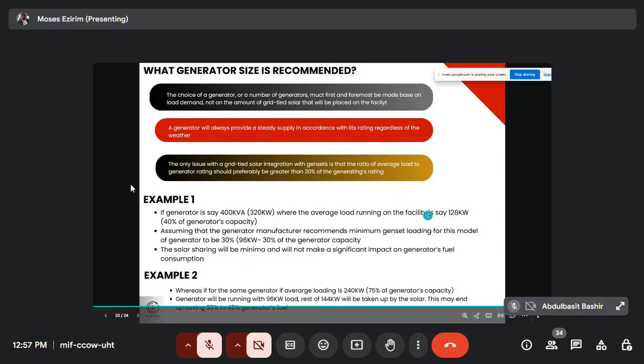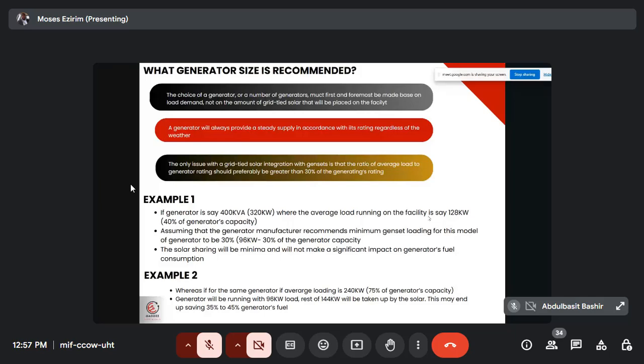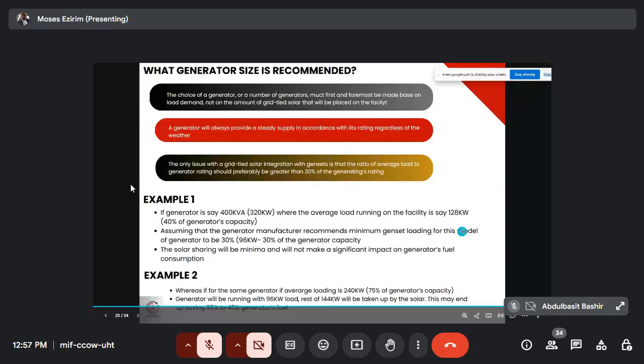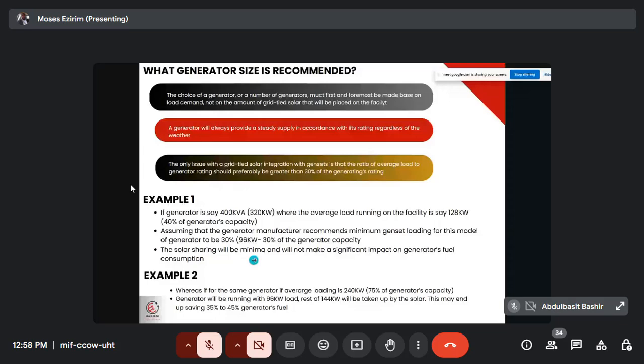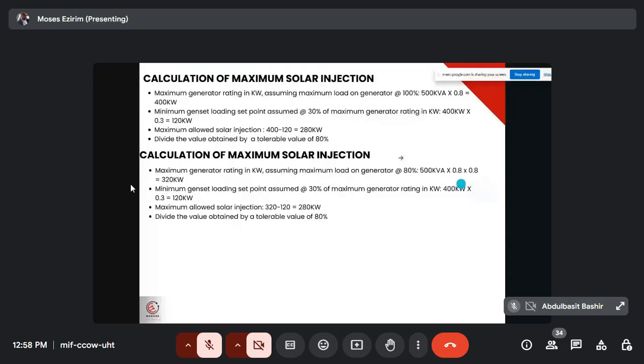Now look at the last example. Whereas if, for the same generator, the average load is 240, the generator will be running 96, that's the 30%. The rest, which is 144 kilowatt, will be taken up by the solar. You can see 144 is significant. This may lead to savings of up to 30 to 40% on generator fuel. So the PV diesel is not just there for show, it is there to make savings. And if the savings are not significant, then there is no point in venturing into it.